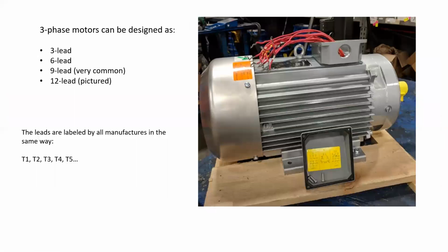Now, three-phase motors can be designed as 3-lead, 6-lead, 9-lead, which is very common, and 12-lead, which is what we have pictured here. They're all three-phase, and there's different reasons for having different numbers of leads, which we will look at in a later presentation. Now, to ensure that the leads are readily identifiable, all manufacturers identify them uniquely in the same way. They're labeled as T terminals, and they're T1 through to T12, depending on how many leads the motor has. A 3-lead motor would be labeled T1, T2, T3. A 12-lead motor would be T1 to T12.